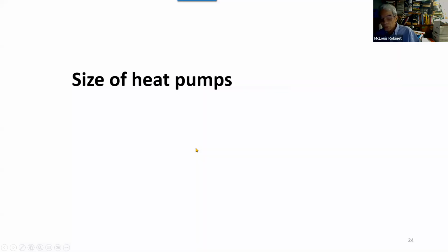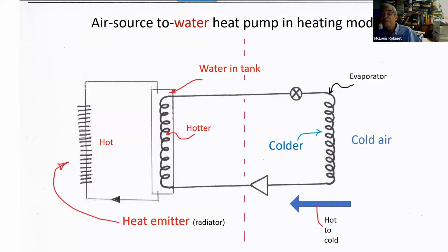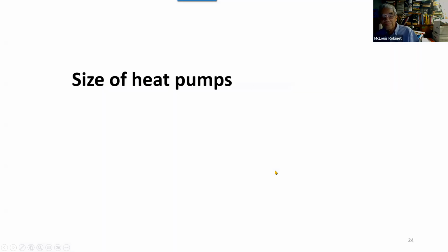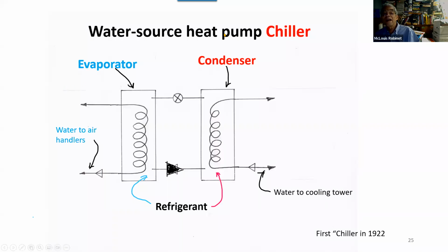Okay, so the size of heat pumps. I mentioned before that, say for a refrigerator or a medium-sized heat pump, these tubes would be maybe the size of a pencil or a drinking straw. But this system is so versatile that it could be any size. Again, my favorite type of heat pump is a chiller, where you have a huge tank here. Instead of a tiny pencil-sized tube, you have tanks you could crawl through. I mentioned a refrigerator might have a pound of refrigerant. You could have these tanks that would have hundreds of pounds of refrigerant. Again, this is the condenser, this is the evaporator. You still have the pump and the expansion valve as before.